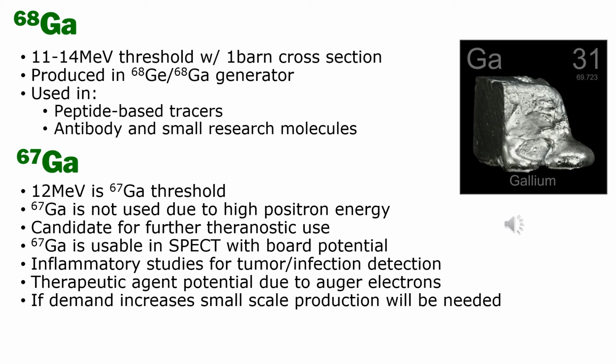Gallium-68 is produced in a germanium-68/gallium-68 generator. It has a short half-life, 67.7 minutes, which prohibits its transportation from a central production facility to an end user. But the germanium-68 parent has a long half-life of 271 days, so gallium-68 just gets produced on site. This shorter half-life is beneficial in that it lowers the dose to the patient from the procedure. Gallium-68 has been produced as a part of various kits and functions extremely well as a radiotracer. Gallium-68 has been recommended to replace indium-111 in neuroendocrine tumor SPECT imaging in the UK.